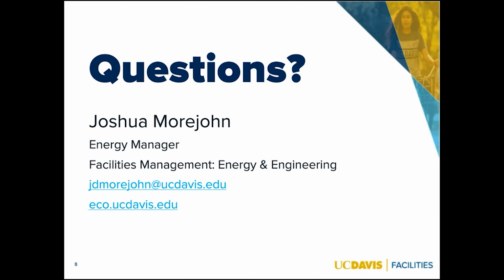Good question. Looking back, we're going through a refrigerant transition right now. If we take low pressure refrigerants, going from R11 to R123 to 514A or 1233ZD, efficiency has gone down slightly, but only by a couple of percent. Going forward, especially with some of the ultra-low GWP refrigerants now available, with GWPs of 1 or 2 and 0 ODP, we can make up for that couple percent loss with better heat exchangers, better compression cycles, and more copper. It's more expensive, but long term I don't see refrigerant, chiller, or heat pump efficiencies going backwards because of the refrigerant.